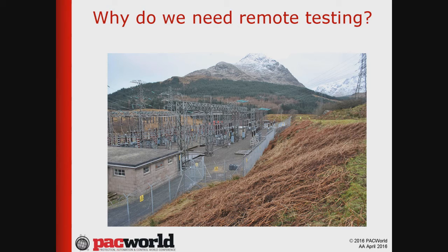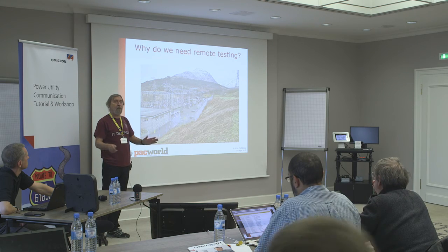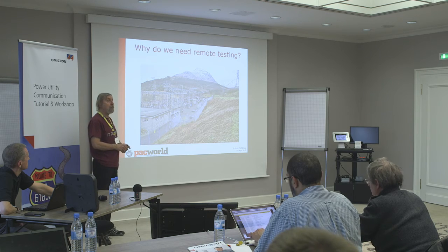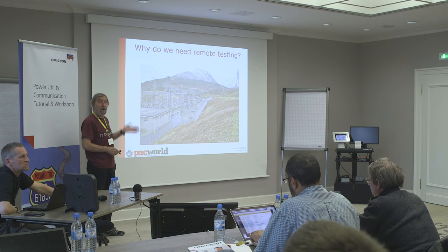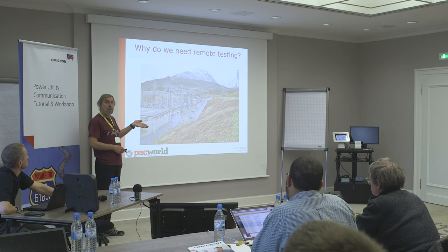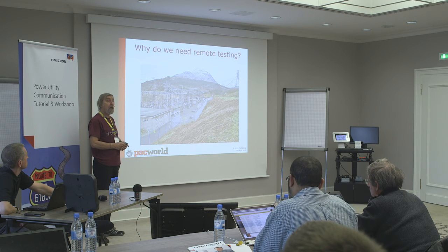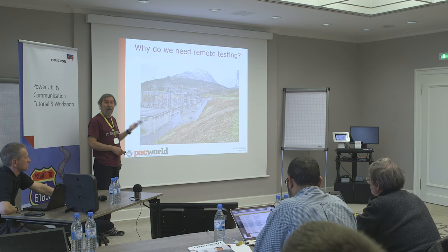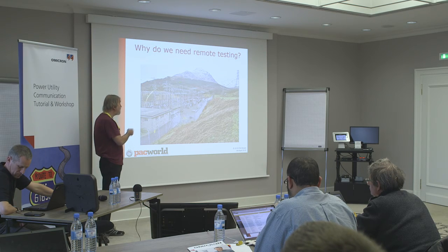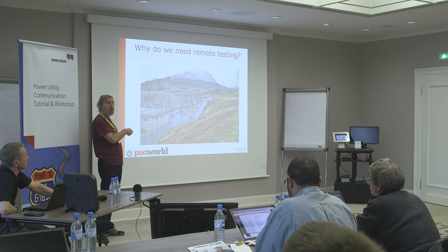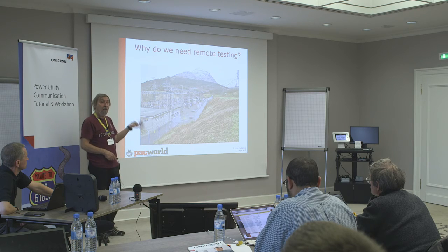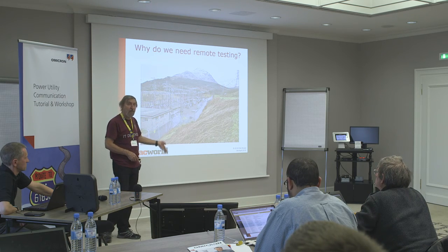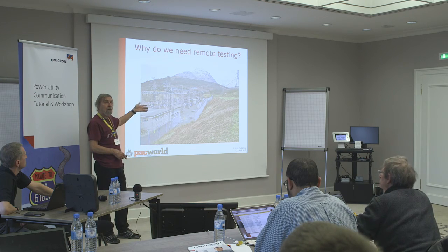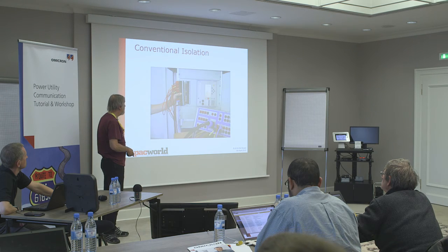Another tremendous benefit of the IEC 61850 digital substation solutions is the ability to do remote testing. And some people may say this is absolutely crazy. But there are crazy people out there. For example, RTE in France are in the process of commissioning right now a substation in France where they want to implement remote testing. Why? Because there are very significant benefits in this technology. Imagine that you have to do testing in a substation in the mountains in the middle of the winter. You have to drive there. It is dangerous. Somebody can get into an accident. It is much more convenient to be able to connect remotely to the substation and run the remote testing there.